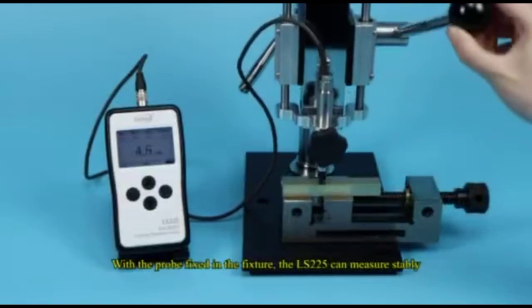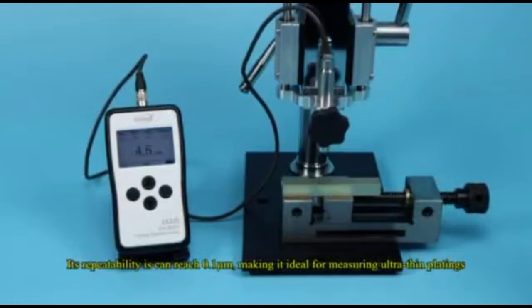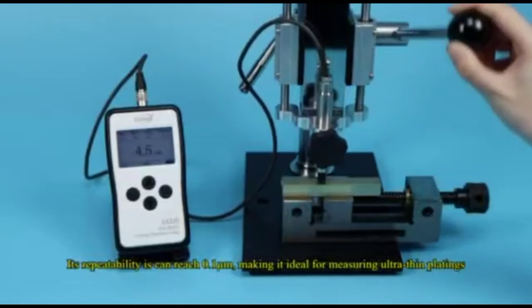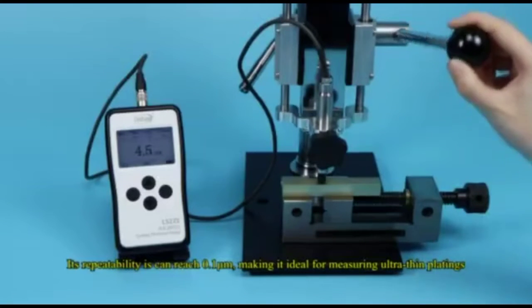With the probe fixed in the fixture, the LS225 can measure stably. Its repeatability can reach 0.1 micrometers, making it ideal for measuring ultra-thin platings.